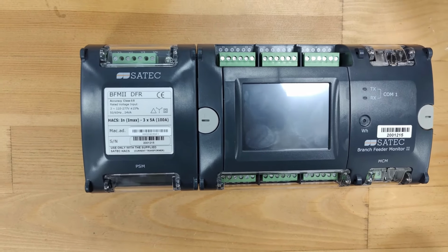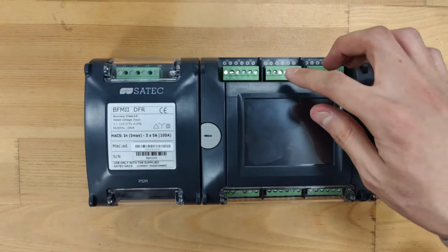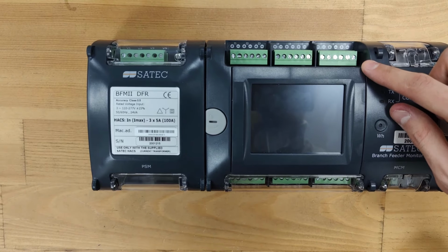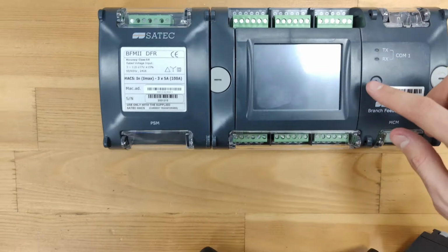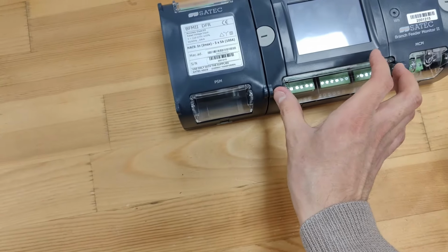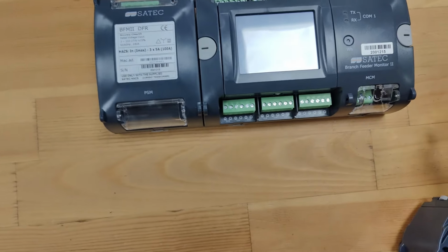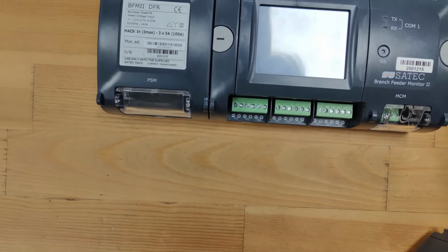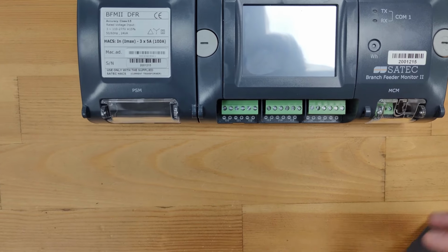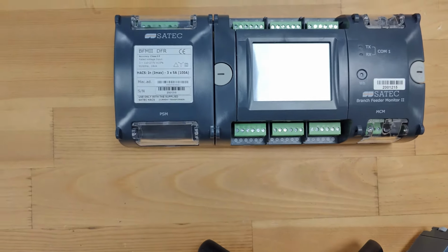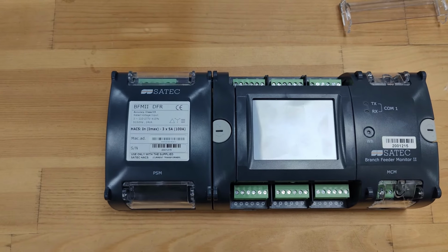Now I'm trying to open these terminals. In the maximum configuration of the BFM II DFR, up to 12 three-phase or 36 single-phase consumers can be connected. The conventional BFM II can even measure up to 18 three-phase or 54 single-phase connections.